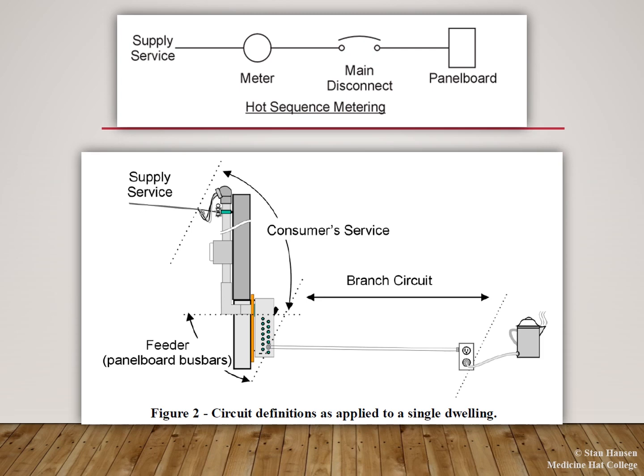For residential construction, we often use what's called hot sequence metering. Hot metering is a typical way that we do residential services because we are already limited in our voltage to 300 volts from line to line, and typically we have less than a 200 amp service. Therefore, we are allowed to do hot sequence metering because the incident energy is already limited by those two factors.